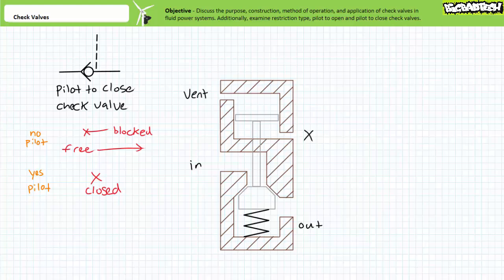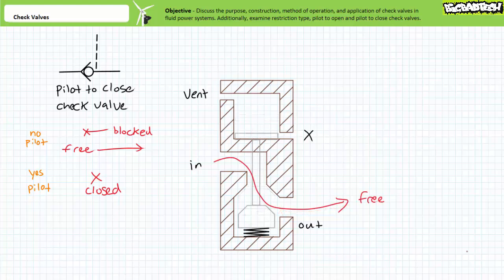A pilot to close check valve can be created using our same diagram by simply swapping the pilot and vent ports. In the absence of pilot pressure, the pilot to close check valve acts just like a regular check valve. In the block direction, the poppet is forced onto the seat and fluid flow stops. In the free flow direction, the poppet is forced off its seat and fluid flows unrestricted through the valve.